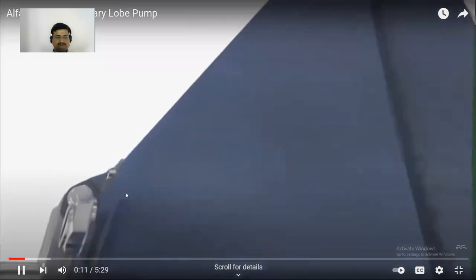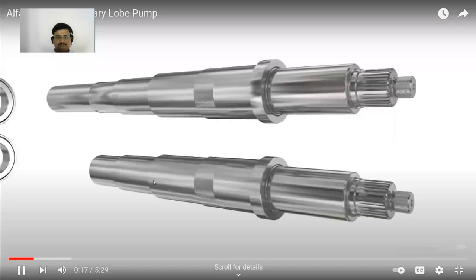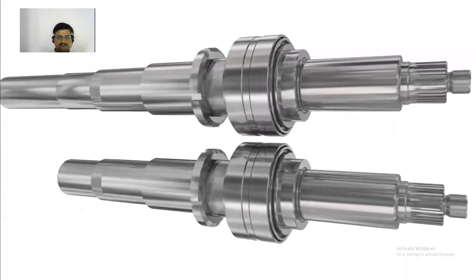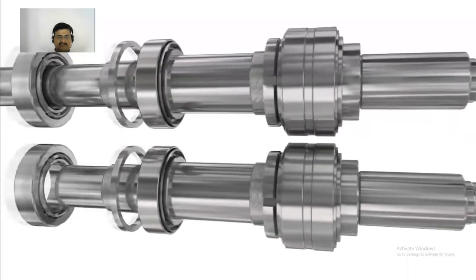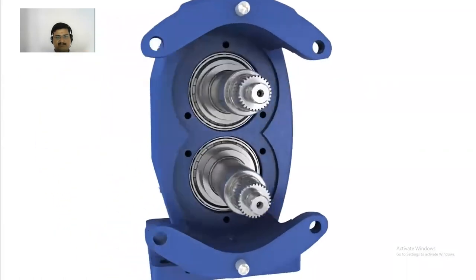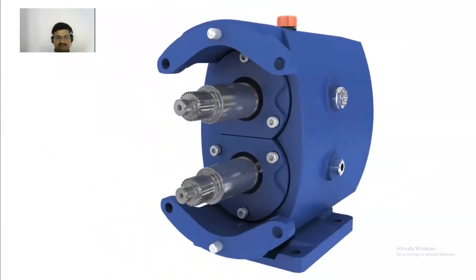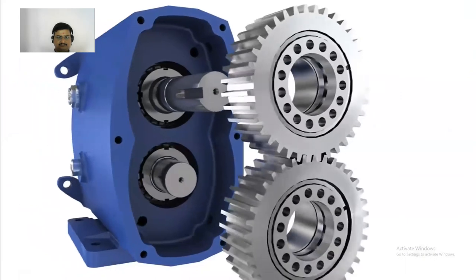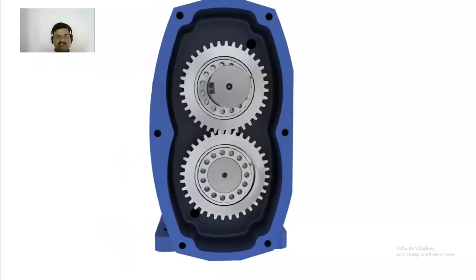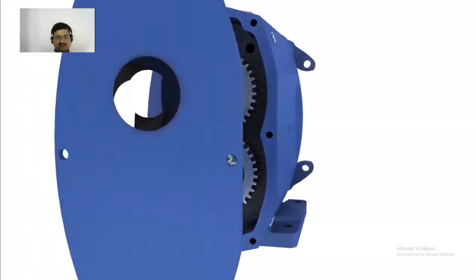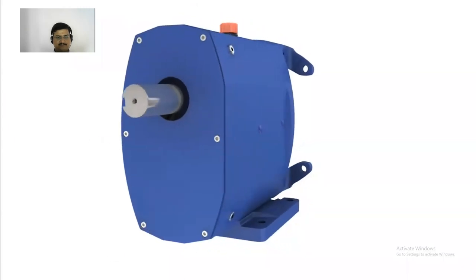Able to handle the widest range of temperatures and pressures, the SIU offers the most extensive options in our rotary lobe pump portfolio. The SIU has heavy-duty shafts and taper roller bearings throughout. These are the rods. And combined with highly simplified construction and maintenance procedures, it reduces the need for maintenance and the risk of costly downtime. And these are the gear mechanism for the proper power transmission.